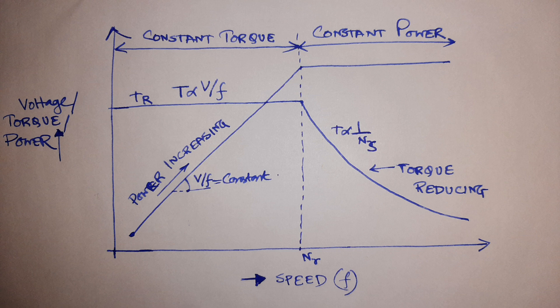the power will gradually increase. Up to rated speed, remember in VFD, if the motor is operated at a reduced speed below the rated speed, it will deliver its rated constant torque but it will take a reduced amount of power, which is mostly used for fan application.